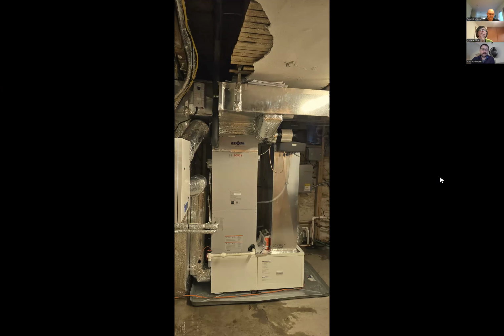This is just another angle from that installation. The current house on that installation actually had a gas-fired boiler existing, and it was just 1 year old. So we ended up utilizing some of that installation as the emergency heater. And that is actually just a hydronic coil that gets connected to the unit. So this system is a two-stage heating system currently now. It has stage one, which is the heat pump, and stage two is the emergency heater, which would still be a gas boiler at this point.